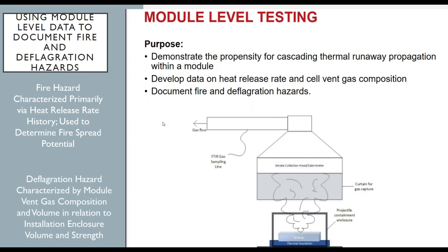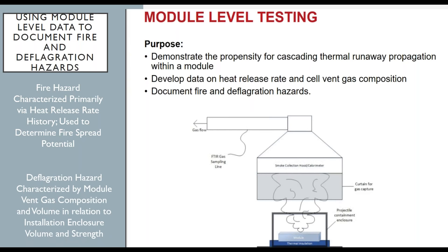So the fire hazard, in this sort of setup, is characterized primarily by the heat release rate, which is calculated online with the UL software in real time. The fire heat release rate is the single most important parameter to characterize the size and threat of any fire, and it can also be used with fire protection engineering algorithms and correlations and general know-how to determine the potential for fire spread and for the threat to the surrounding enclosure and to any nearby occupants or target vulnerable equipment.